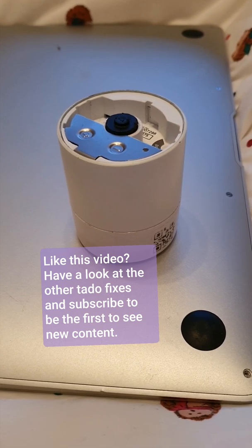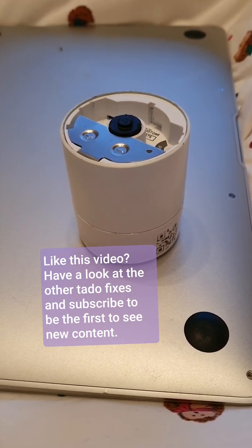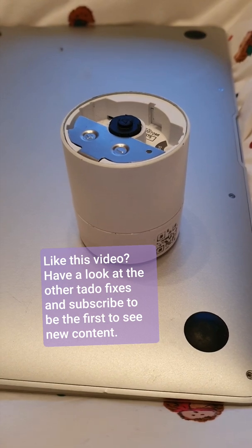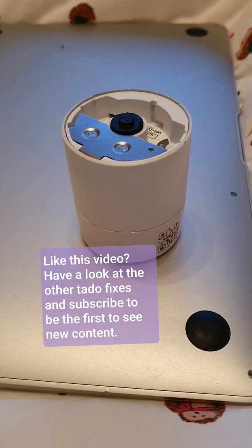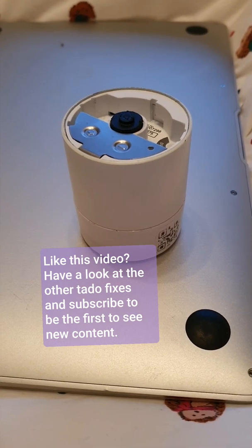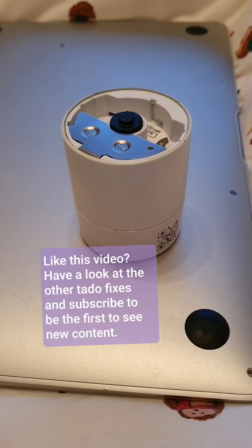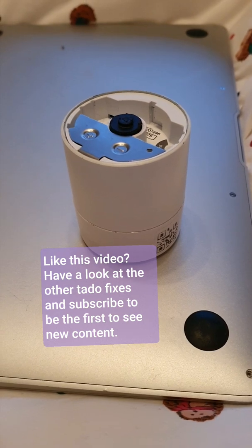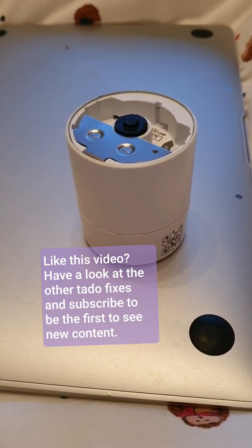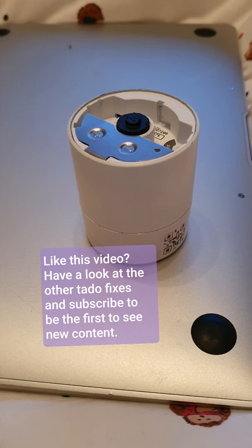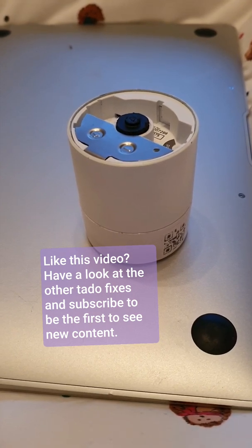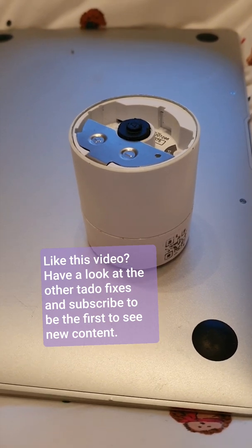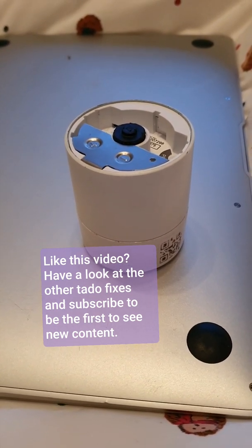So I went on to the command unit. When I asked for heat, I can hear the relay switch clicking on and that unit will then send a message to the boiler to say, power up. So we're assuming that the boiler is getting a signal from that little unit next to the boiler, the little rectangular unit. But why was it not switching?